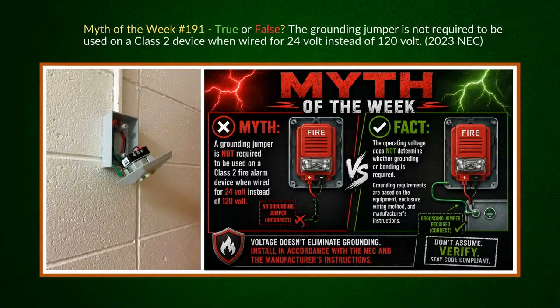But it's a pretty interesting question because at 120 volts, that could be parts that are likely to become energized. Those door magnets are energized to hold the door, so they're pretty much 24/7 energized unless the fire alarm goes off. Just off the top of my head, it has a screw hole, the manufacturer requires that jumper, and basically designs that as a listed assembly. So you have the door magnet itself, the device that goes in the box, they all fit together, and it's designed to have that jumper in case parts are likely to become energized. I don't think that really has a voltage threshold for class 2 wiring or class 1 wiring.